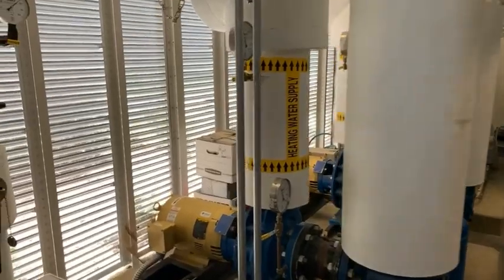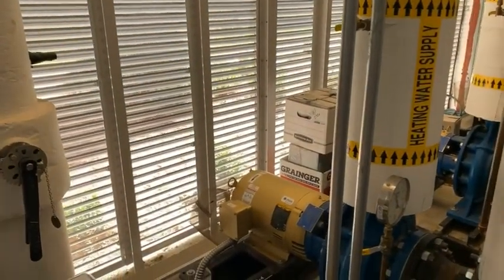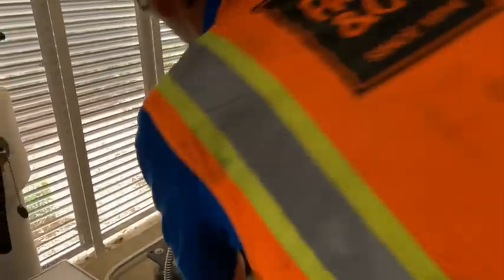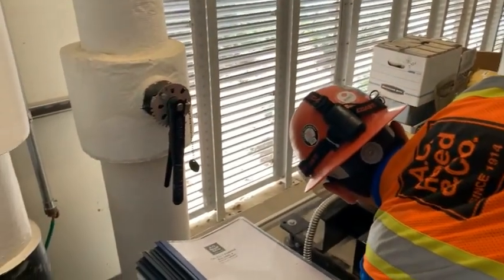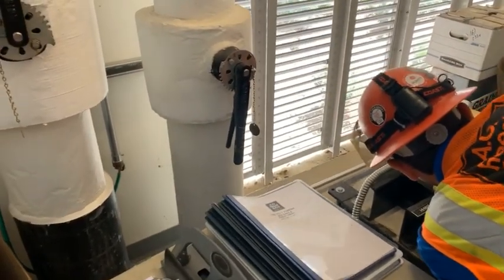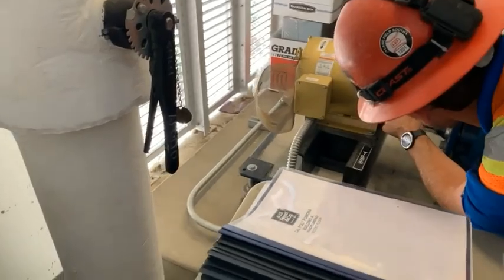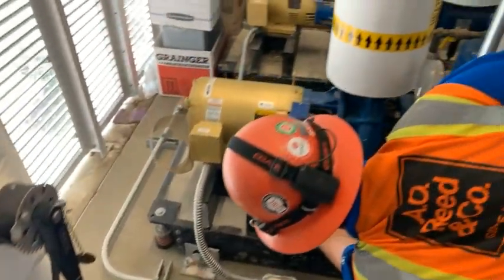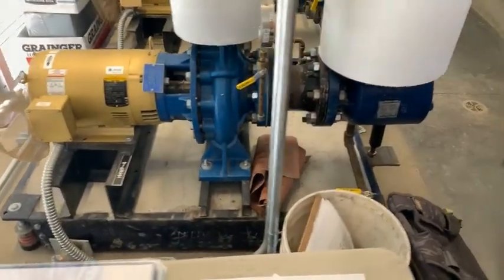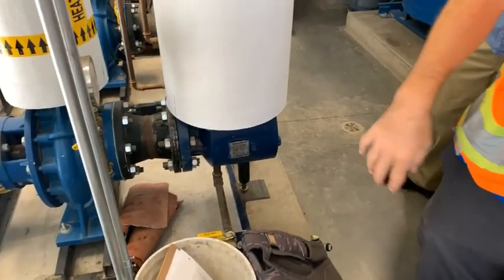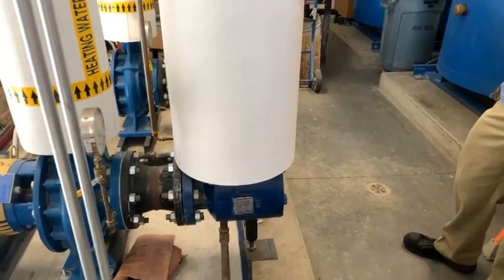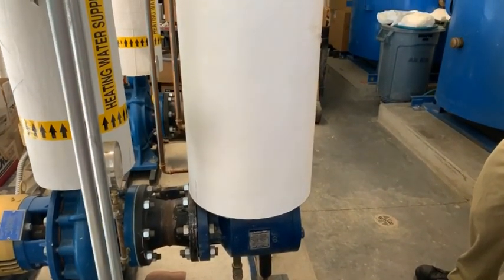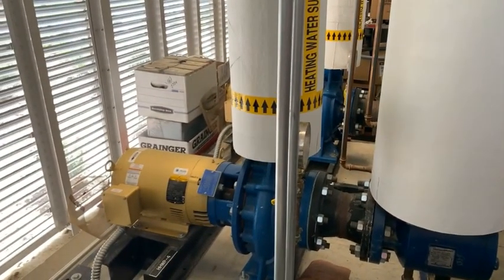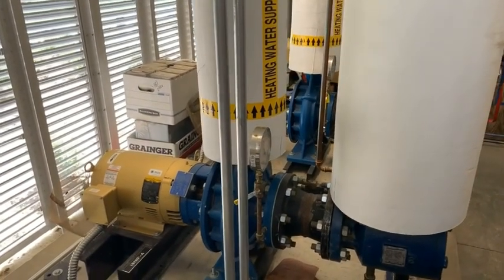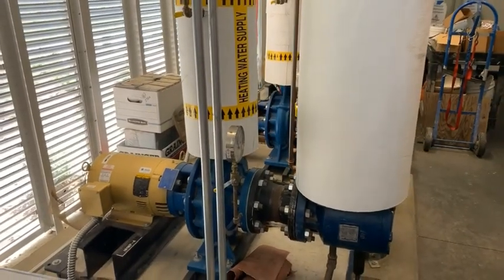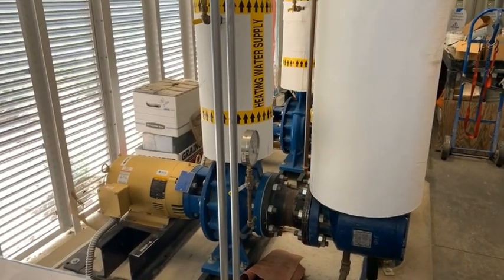Let me see if we grease. And then you can reset the run hours. It'd be like once a year normally, or X amount of hours. Yeah, I don't know, 3,000 or whatever. They have the bearings listed on here, but not the grease. So we'd have to look in the O&M manual for the type of grease that they recommend. Okay. And then how many squirts, because it's all going to be super variable on what type of grease gun you're using and all that, right? Every grease gun distributes a different type of grease, a different amount of grease.